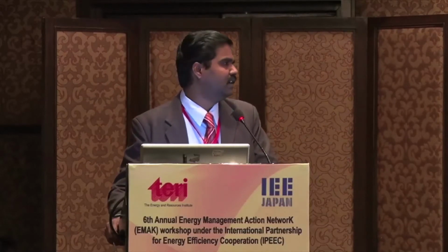And this is the first plant in China. It has been in operation since 1998, which is for more than 15 years. And the rated capacity is 6.5 megawatt. Here you can see the operational statistics for the 15 years, from 1999 to 2013. You can see the design value for the total output is around 4,087, but the actual output is 5,448, which is much higher than the design value. And the capacity is designed for 6.5 megawatt, but the actual generation is around 6.9 megawatt. And the availability is 94% design value versus an actual of 97.58%. And the output per ton of clinker is also about 10% higher per kilowatt per ton.